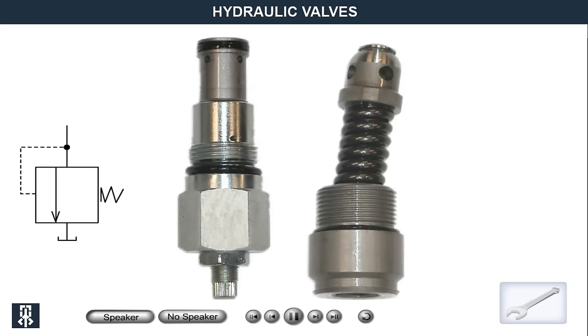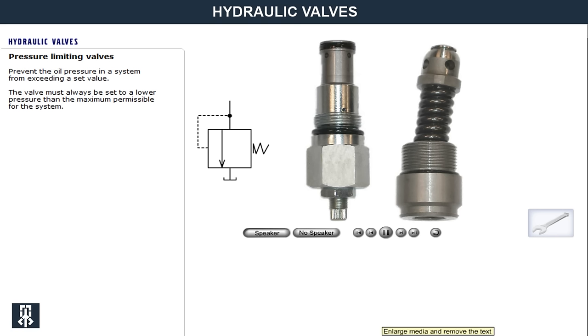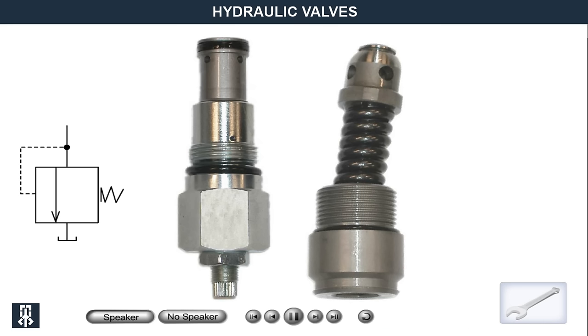The function of the pressure limiting valves is to prevent the oil pressure in a system from exceeding a set value. By the spring being compressed when the valve opens, the pressure at full fluid flow through will always be higher than the opening pressure. Since the opening pressure is lower than the flow-through pressure, the valve must always be set to a lower pressure than the highest permissible for the system.